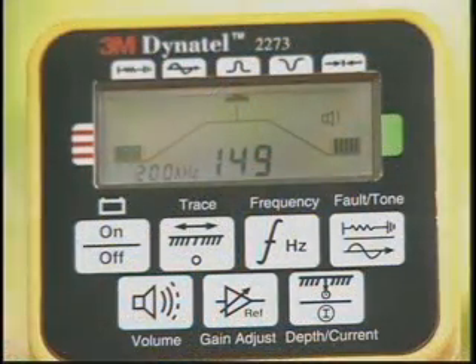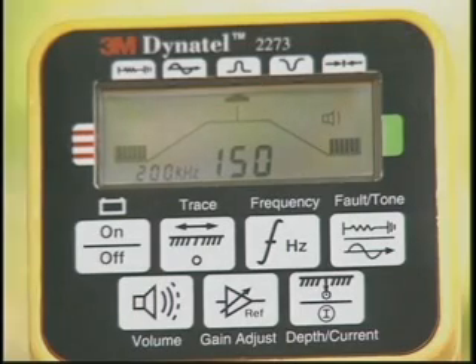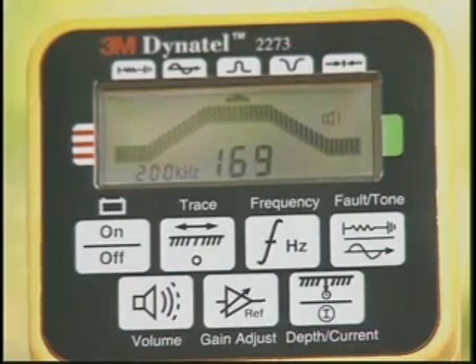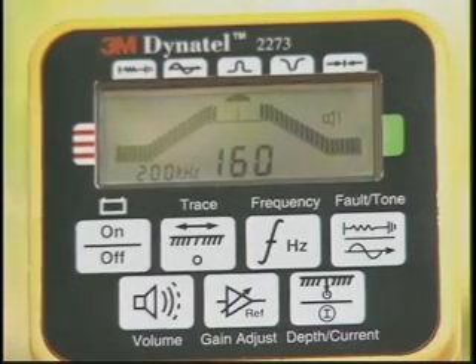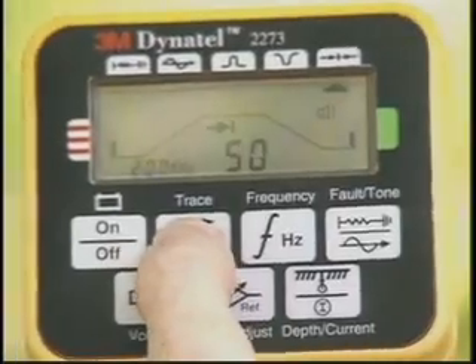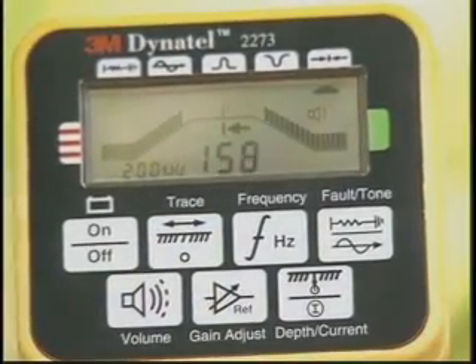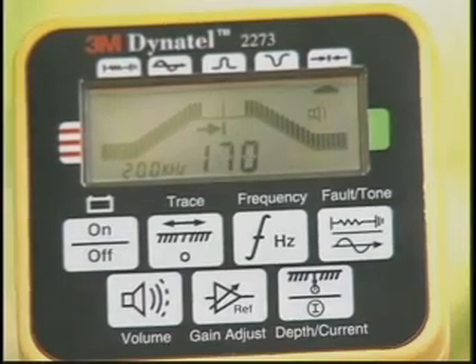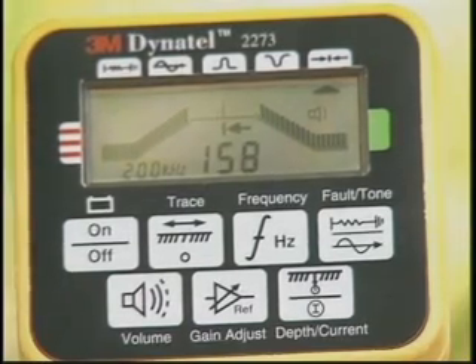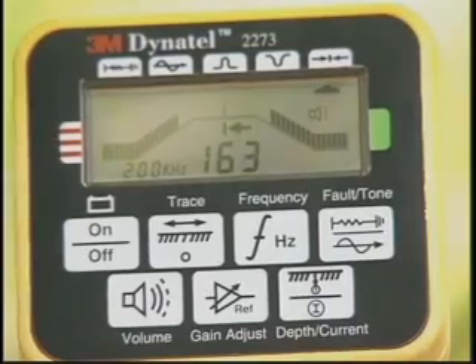When you're tracing a conductor, this bar graph and numeric indicator shows the signal strength, which is at a maximum when you're over the cable in peak mode. And there's an audio response that gets louder as you get closer to the conductor. In addition, there's a directional or differential mode that points to the cable's location. In this mode, the unit makes a distinctive warbling tone as you move to the left or right of the cable.